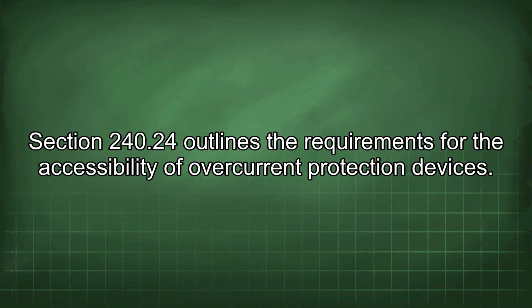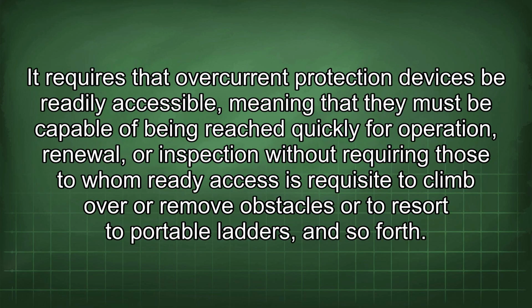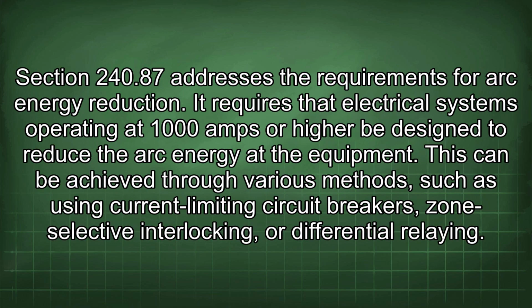Section 240.24 outlines the requirements for the accessibility of overcurrent protection devices. It requires that overcurrent protection devices be readily accessible, meaning that they must be capable of being reached quickly for operation, renewal, or inspection without requiring those to whom ready access is requisite to climb over or remove obstacles or to resort to portable ladders, and so forth. Section 240.87 addresses the requirements for arc energy reduction.